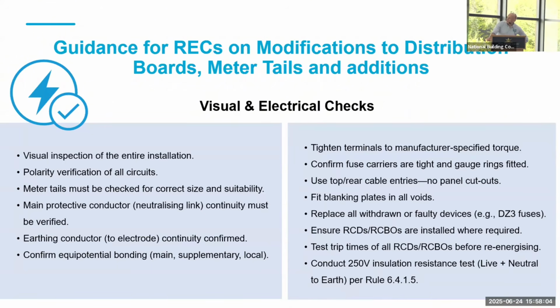Ensuring that the RCDs and the RCBOs, so that's referring to the trip switch, making sure that they're all installed where required, and the test times on these RCBOs are all checked and recorded, even on existing ones. So even if they're just putting in their own RCBO for the car charger, we're also asking them, while they're at the distribution board, to carry out tests on the other type RCDs.